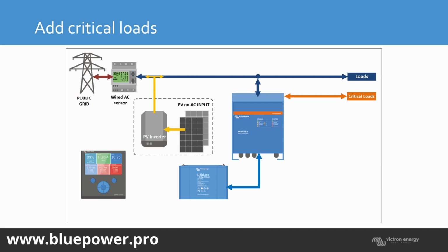And we can also add critical loads onto our backup system. So that's computer, lights, fridge. So that's on a limited system. So the loads on top are fed directly from ESCOM, non-essentials, and then the critical loads are only fed from the battery when there's a power failure, or when you're running ESS and it's set to feed power from the battery.